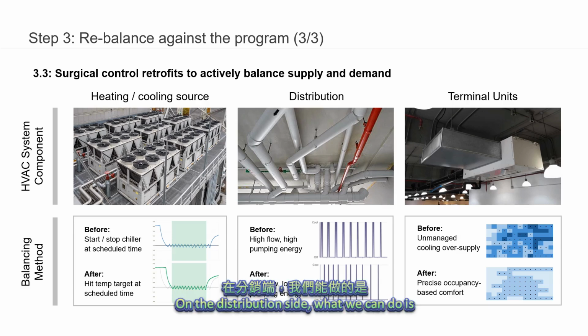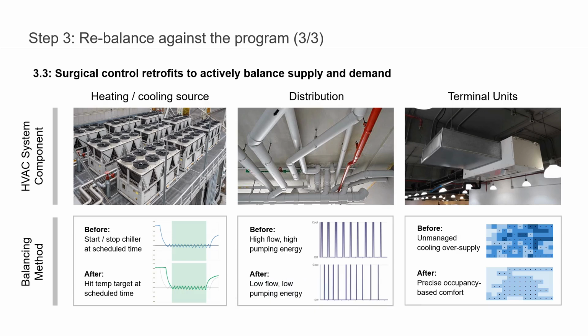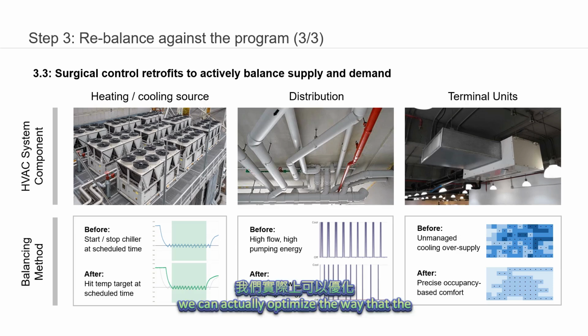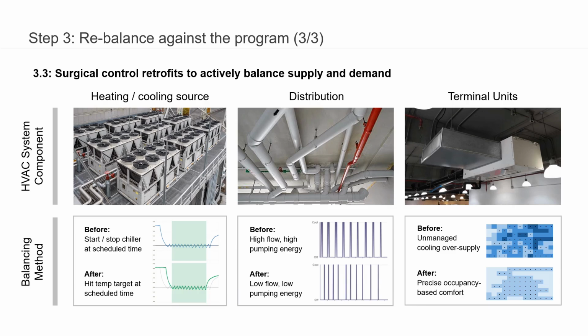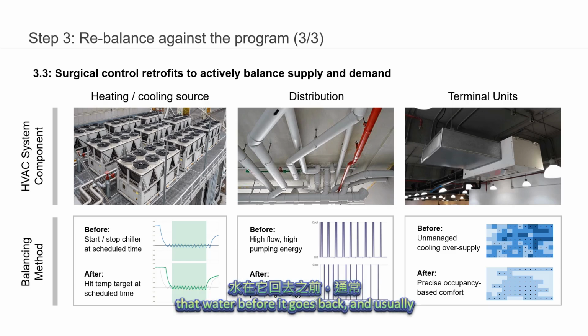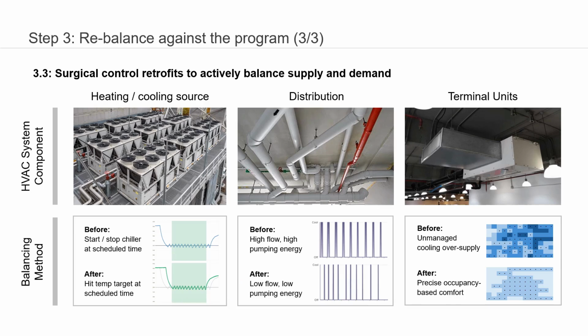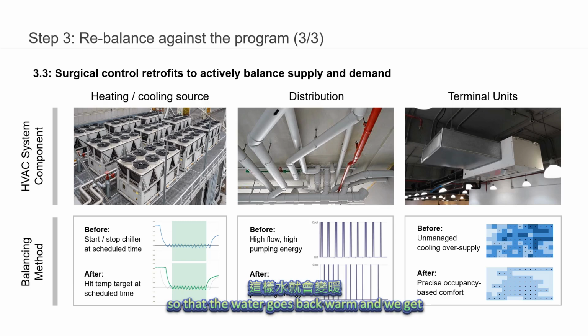On the distribution side, while maintaining balance in each space, we can optimize how water flows through the pipes. Often, as with systems in this room, the water flows too fast, so we're not extracting all the cooling before it returns too cold to the central plant. By fine-grained control, we can slow the water flow and pull more cooling per cubic meter of water, so it returns warmer and we get as much cooling into the room as possible — with much less flow in the pipes, saving money on pumping.